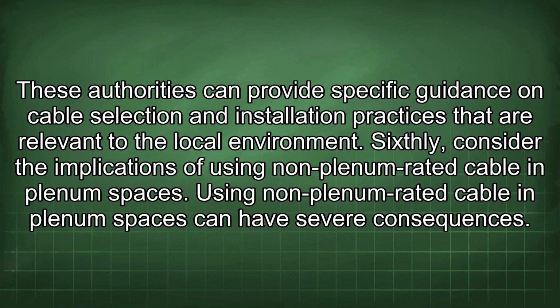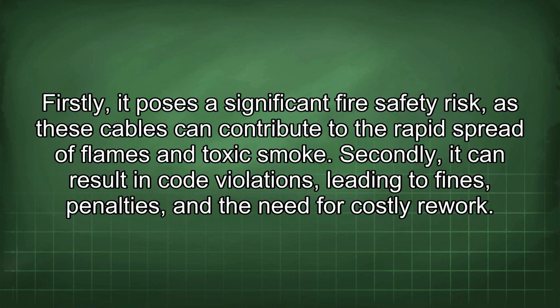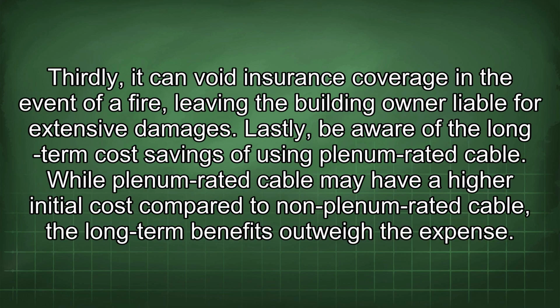Sixthly, consider the implications of using non-plenum-rated cable in plenum spaces. Using non-plenum-rated cable in plenum spaces can have severe consequences. Firstly, it poses a significant fire safety risk, as these cables can contribute to the rapid spread of flames and toxic smoke. Secondly, it can result in code violations, leading to fines, penalties, and a need for costly rework. Thirdly, it can void insurance coverage in the event of a fire, leaving the building owner liable for extensive damages. Lastly, be aware of the long-term cost savings of using plenum-rated cable.